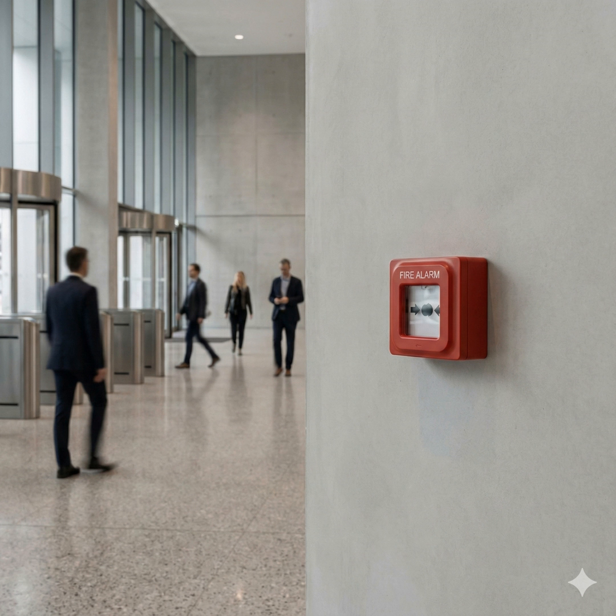It's so much more than a simple switchboard. When it gets a signal from a sensor, let's say a slight obscuration reading from a photoelectric chamber, the panel evaluates that signal against these complex, pre-programmed thresholds and logic sequences before it decides to activate anything. So it's running a constant real-time risk assessment. It is, based on its internal logic, which is crucial for telling the difference between a minor event like some steam from a shower and a genuine fire threat.